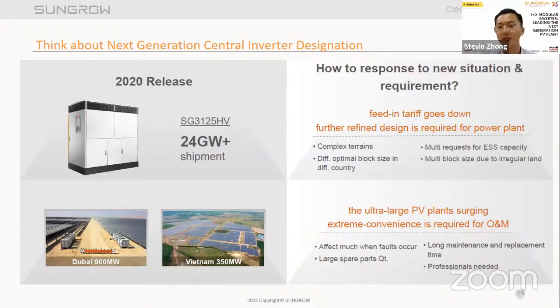The first point is that the feed-in tariff goes down. The other point is that some factors require the power plant to be more refined in design, such as complex terrains, different optimal block size in different countries, ESS capacity, and the multiple block size due to irregular land. There's also a trend that the ultra-large PV plants is surging, which poses requirements for the operation and maintenance to be more convenient. When faults happen in the system, it may affect much of the project, so the maintenance and replacement time would be longer. Professionals are needed as well, and the number of spare parts would be larger.